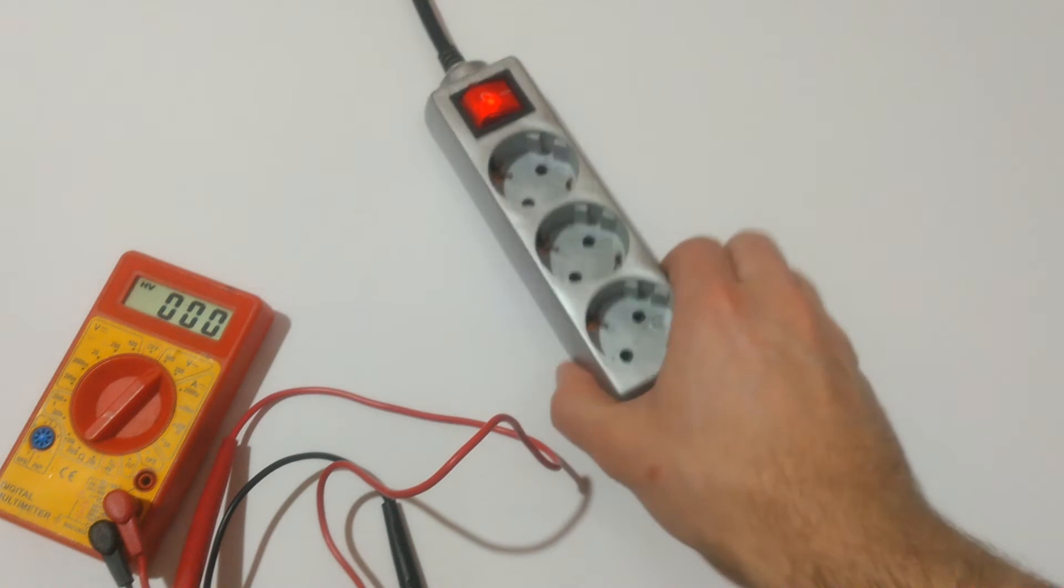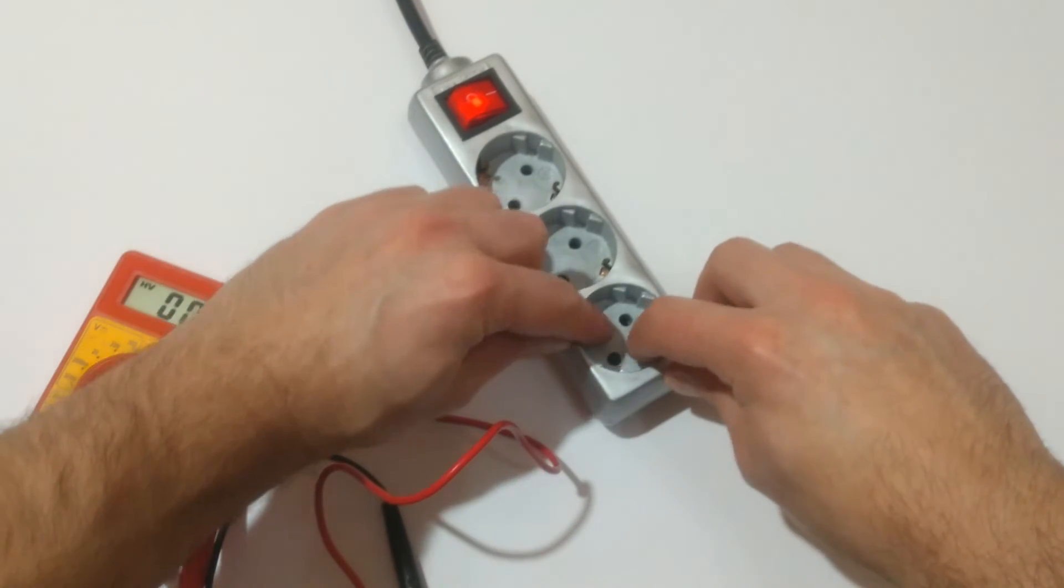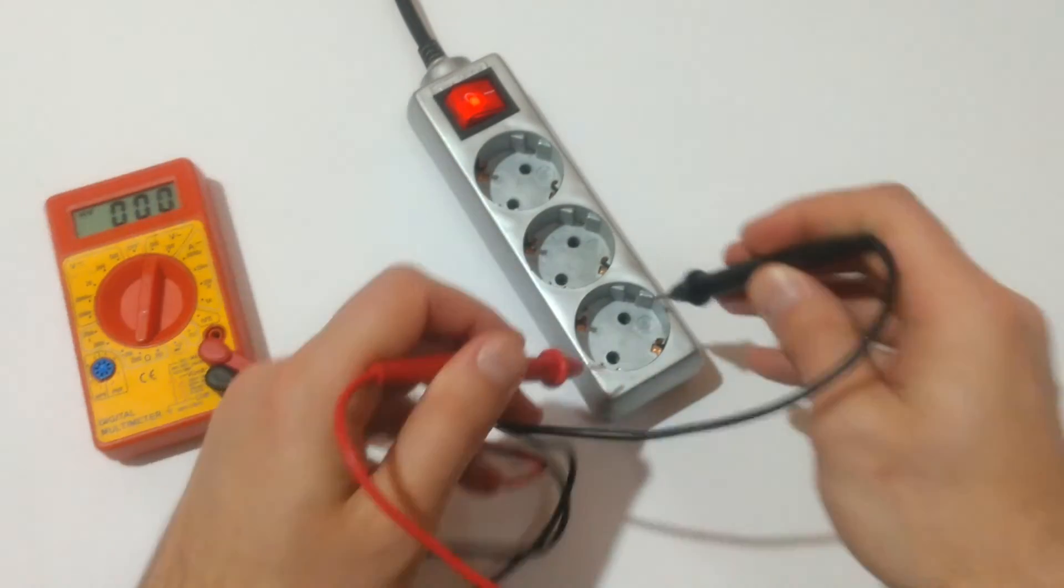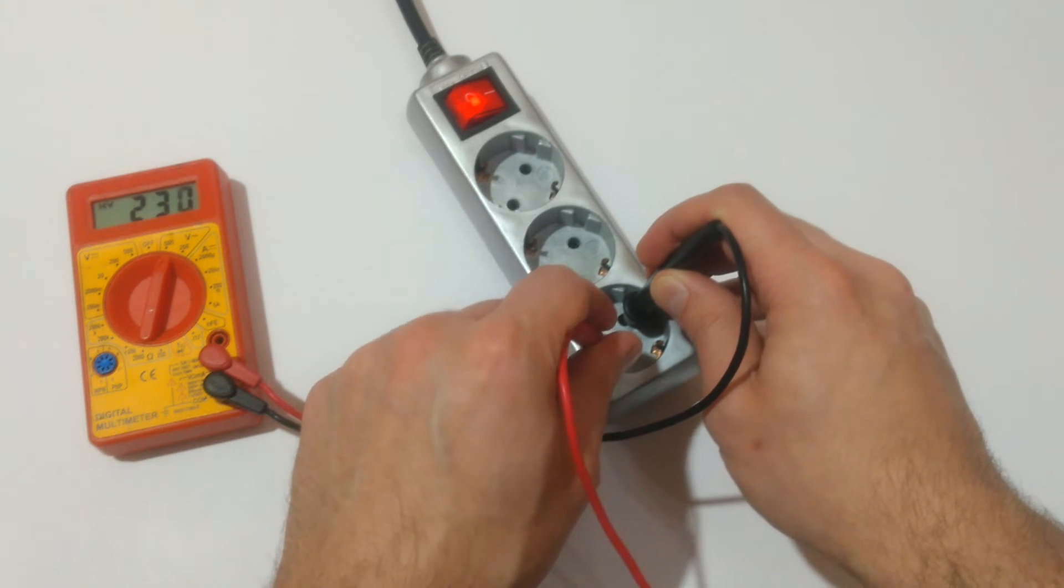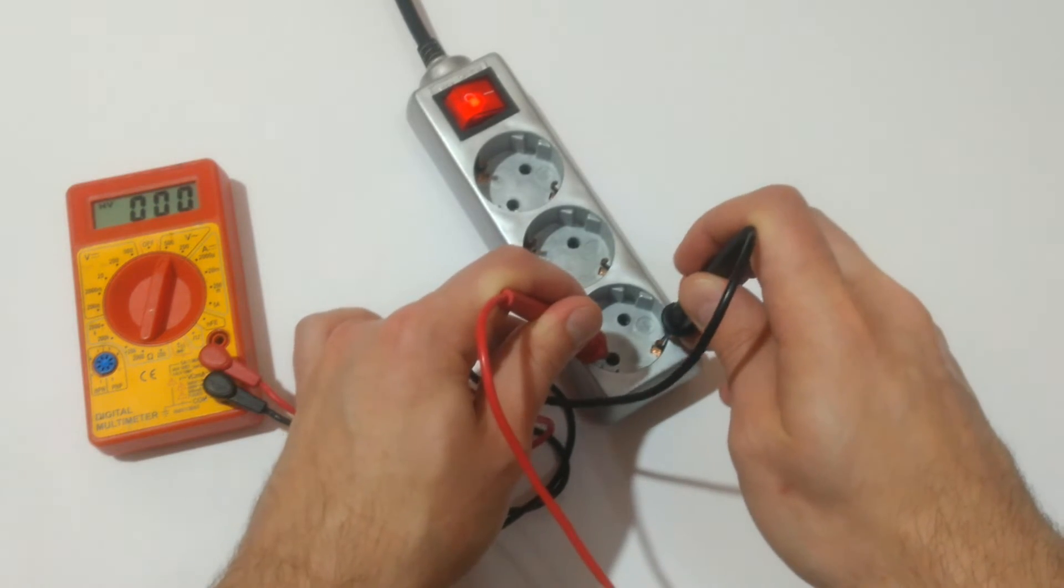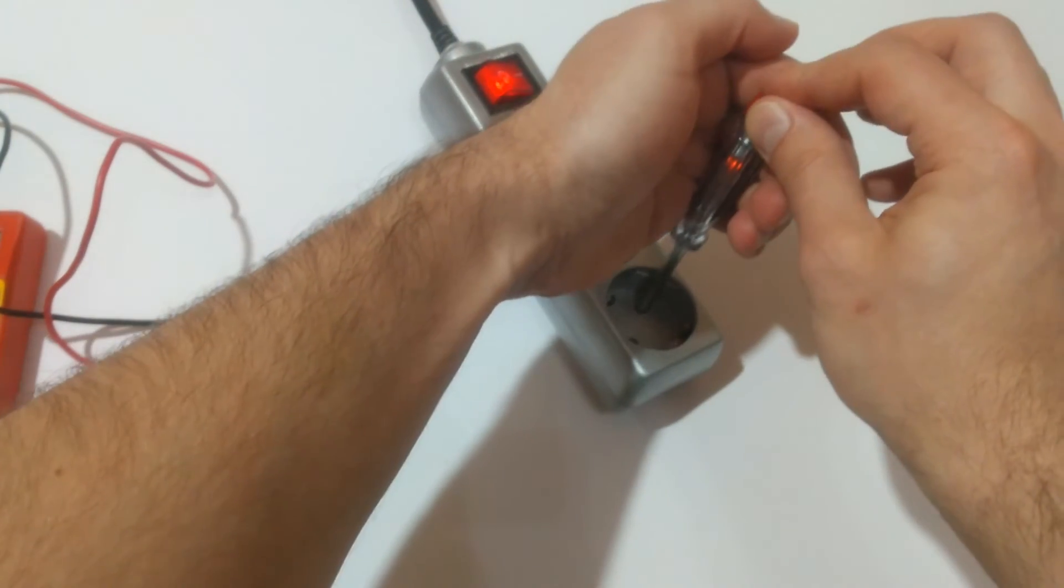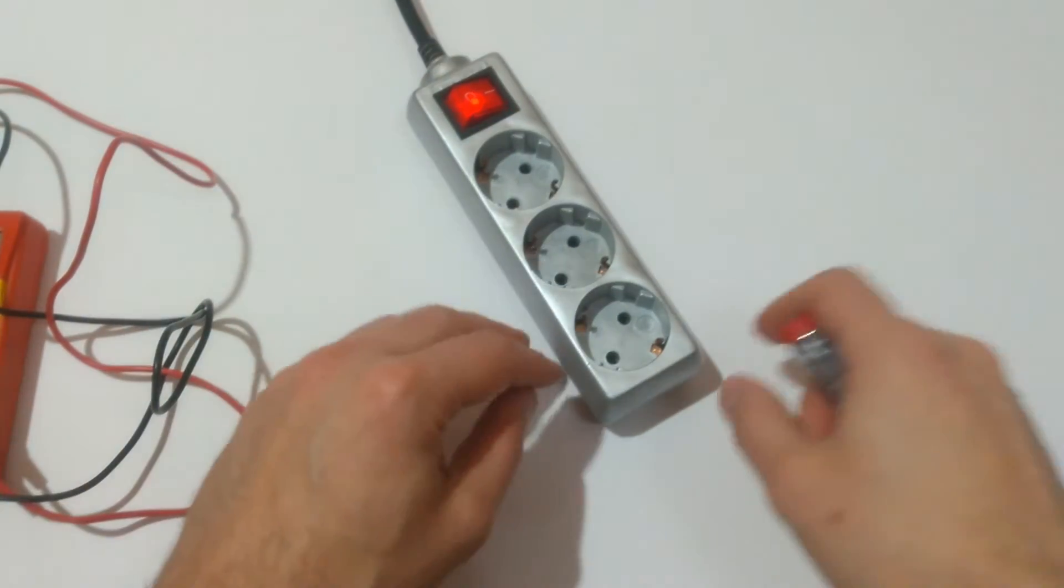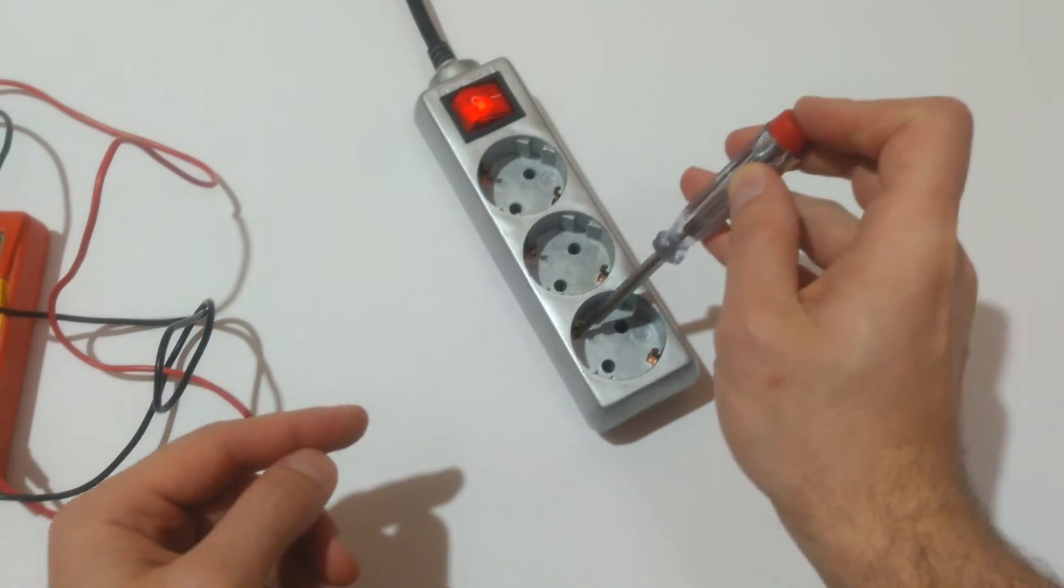Let's do the same test with the same power strip but without proper grounding, proper earthing. Those two conductors over here are not connected. Let's check the voltage. 236, 237 fluctuating. Nothing here and nothing here. This is the live conductor. Neutral and due to those two not properly connected, here we have a slight phasing I'm not sure if you're able to see it.